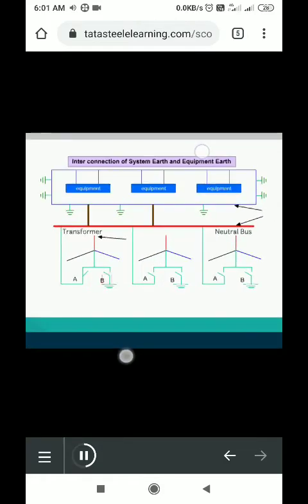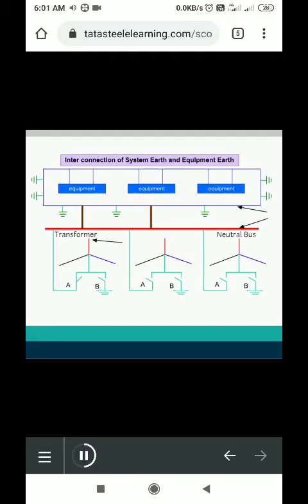Let us say this is an equipment pit wherein the non-current carrying parts are grounded. You can also see that there is a neutral bus bar and further there is a neutral pit. Here we can see that the live part is grounded. Now suppose there is some maintenance work or testing to be carried out near the neutral earth pit, suppose pit B. Since it is connected with the live part, the testing or maintenance cannot be done online. This connection needs to be isolated first. However, isolating it will destabilize the power system.